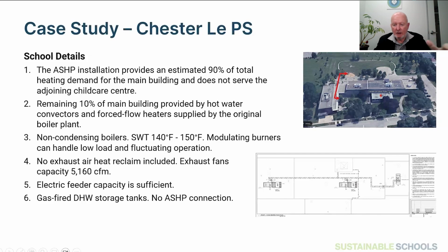But just very generally, you can see the school in the picture at the top. There's a daycare on the left-hand side that did not get converted to air source heat pump. The 2 units and the one on the right-hand side in the gym, those are the 3 units that were put in. These units are very atypical. These are multi-zone air handlers back in the day, so it's not like a normal rooftop unit conversion, but it's a wonderful example of tracking through these steps within the whole process.